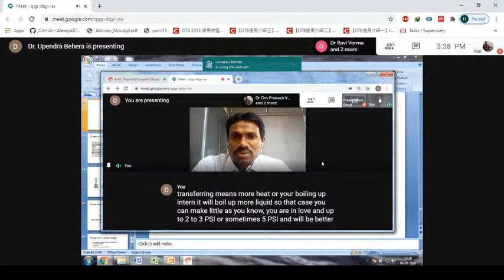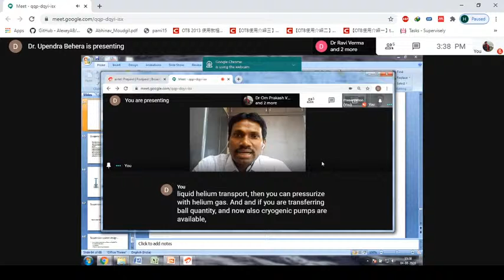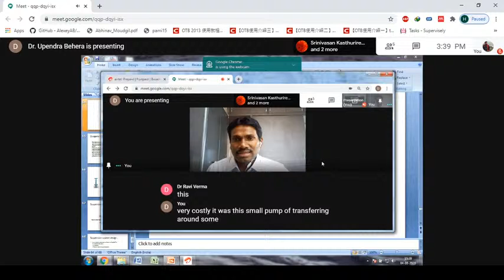And the second one is external pressurization. As I told, you can use cylinders of the same gas. If it is liquid helium transfer, then you can pressurize with helium gas. And if you are transferring bulk quantity, cryogenic pumps are now also available. With that, you can transfer cryogens, and this is specially used for high flow rates, because these pumps are not so cheap. For my vortex tube experiment, I was trying to procure a LOX pump, and it was very costly. It was a small pump transferring around 10 cc per second. It was costing around 10 to 15 lakhs.